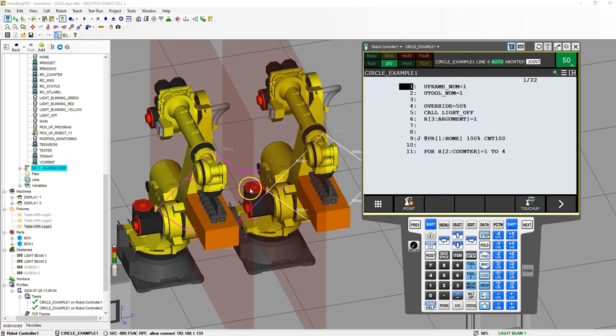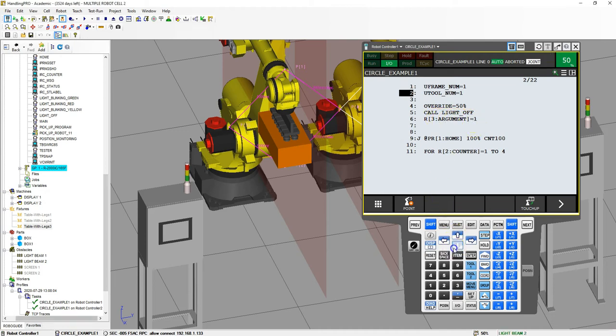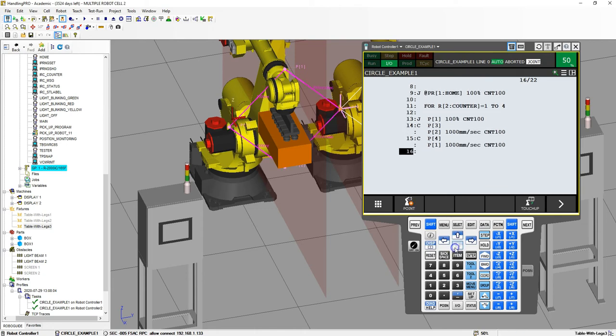Just as a review, I have two circle programs — a circle program on robot one and a circle program on robot two. I have robot one running at an override of 50% and robot two running at override of 70%, which is why robot two ran a lot faster. At the beginning, we are calling a light off. In previous videos we had the light blinking, but now we're switching it to a digital output to communicate to the other robot, with an argument set to one meaning the robot is running. We're doing the circle loop four times with a for loop and a counter.